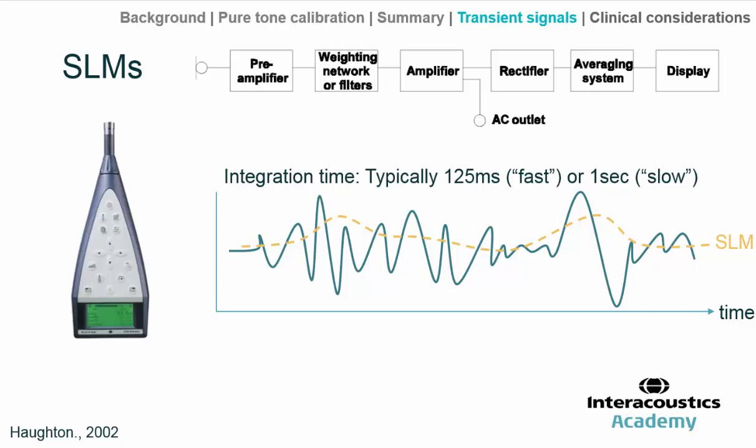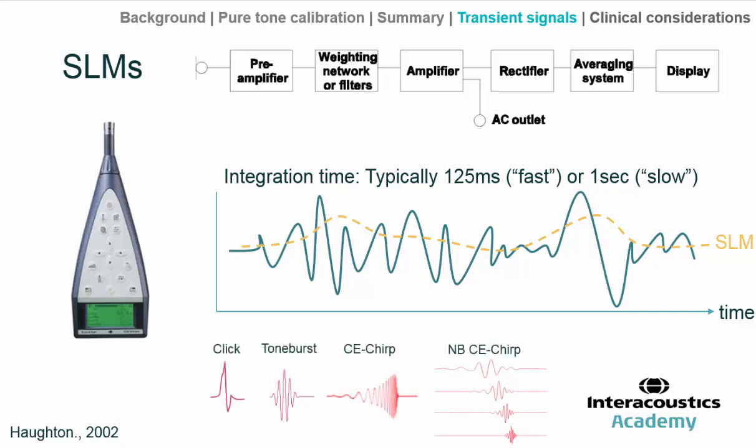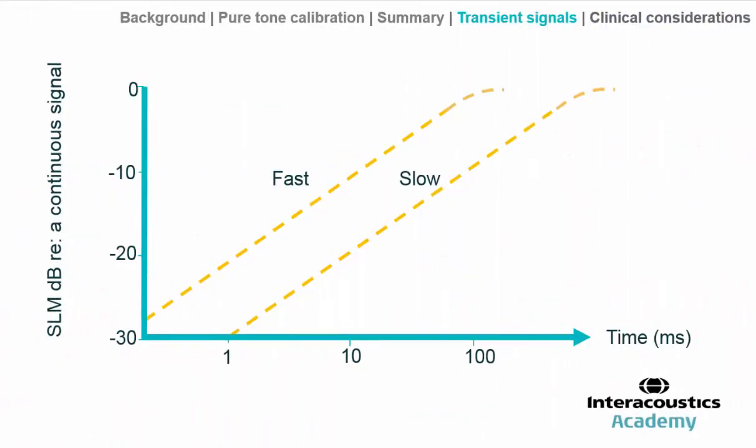For example, clicks, tone bursts, and chirps of various types that are commonly used — if the signal is much shorter than the integration time, the sound level meter will likely underestimate the true level of that signal. On the chart shown, the x-axis shows the duration of the signal and the y-axis shows the degree of underestimation relative to a continuous signal. As the stimulus gets shorter, or as the integration time is more and more unfilled, the underestimation of the level gets greater and greater.